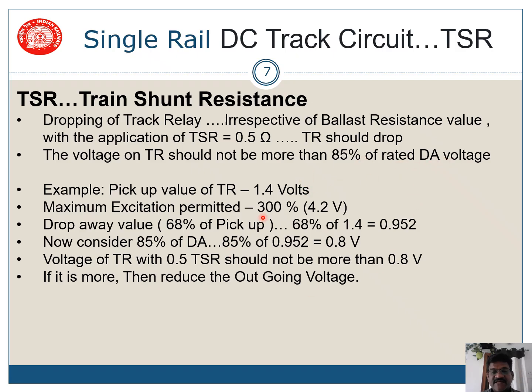Here is an example. The pickup value of the track relay is 1.4 volts and the maximum excitation permitted, which is 300% for QTA2 relay, is 4.2 volts. The drop-away value is not generally given, so we take it as 68% of the pickup value, which comes to 0.952 volts. Now we calculate 85% of the drop-away value — 85% of 0.952 is 0.8 volts. So the voltage on the track relay, when a 0.5 ohm TSR is connected across the track, should not be more than 0.8 volts. If it is more, you have to reduce the outgoing voltage.